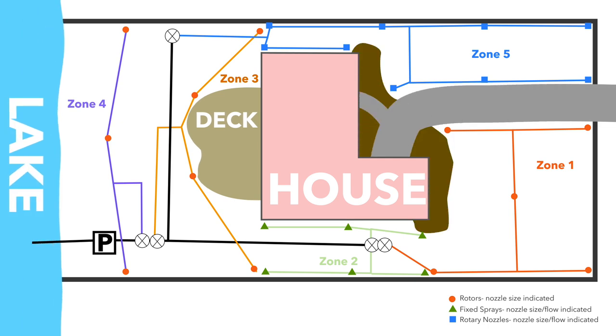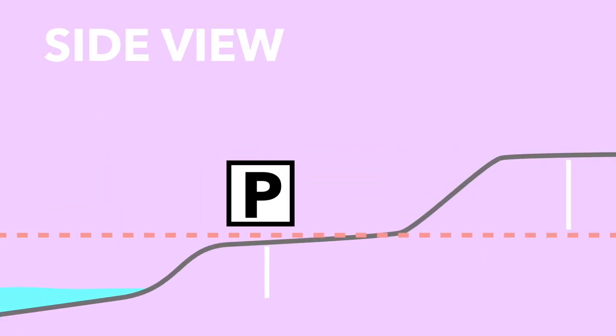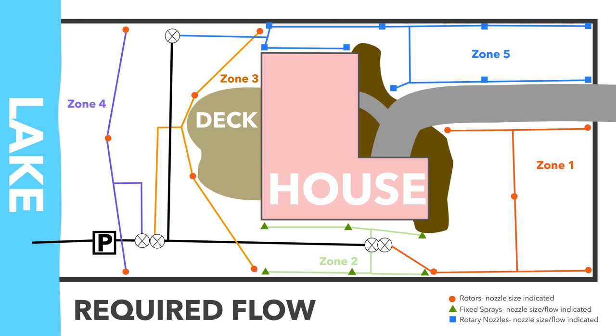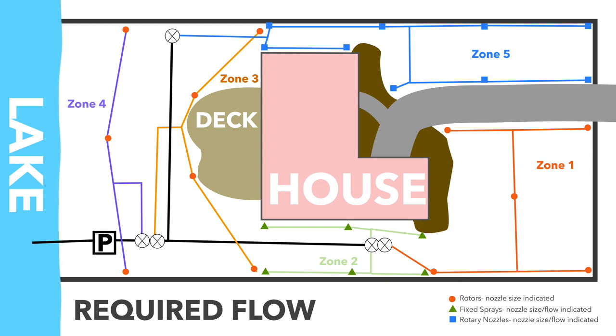Let's work through an example: selecting a pump for an irrigation system at a lake house. The property has significant elevation changes — it rises four feet off the lake, levels at the deck, then rises an additional eight feet to the street. The first step is calculating the required flow by finding the zone with the highest flow rate. Zone 1 has four rotors at 1 GPM each and one at 4 GPM, totaling 8 GPM.